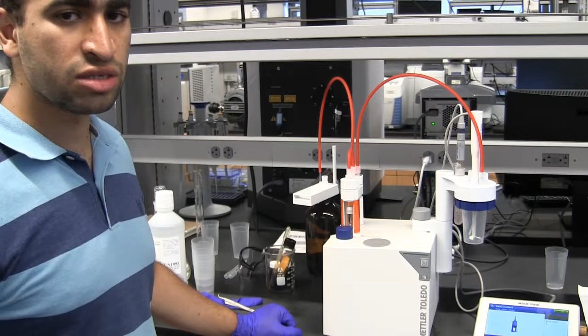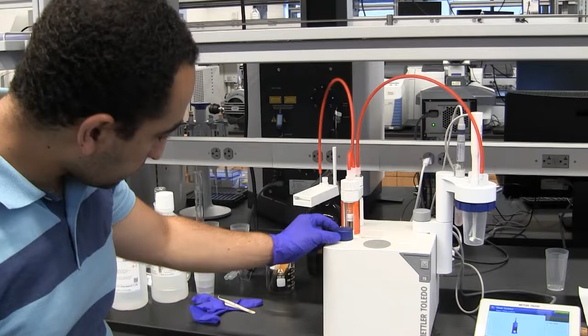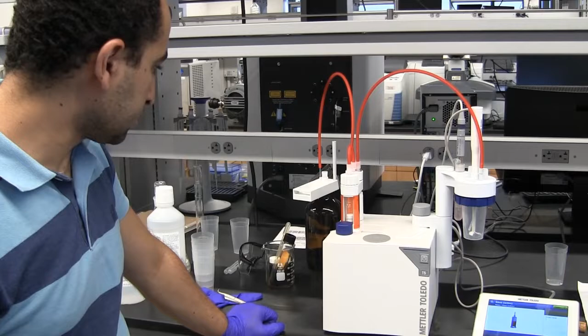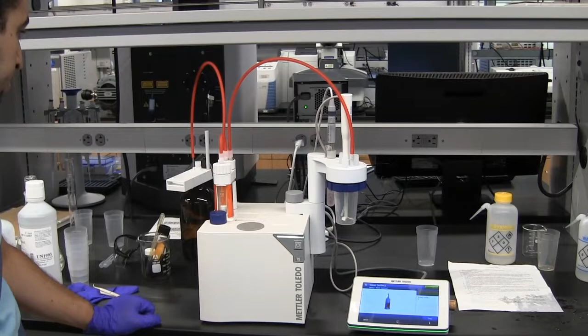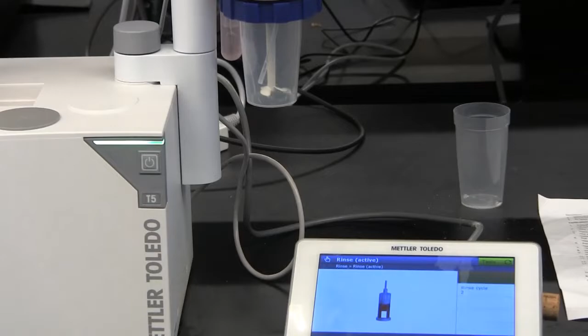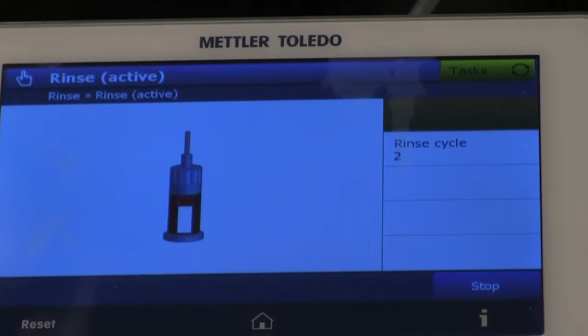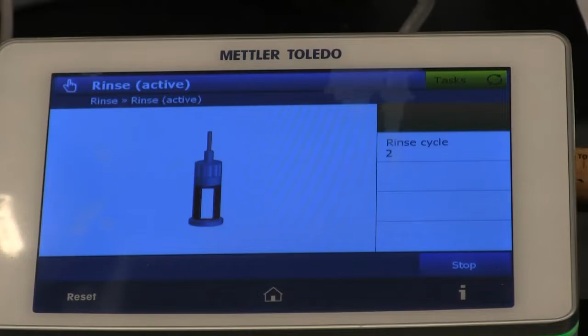Any residue will just be swept away. So now it will do 3 cycles. Yeah, now it finished the first cycle. It's running the second. So until now it's just cycling here. Make sure also there are no leaks, so all lines are connected properly, because if any line is not connected properly, it's just going to cycle air.